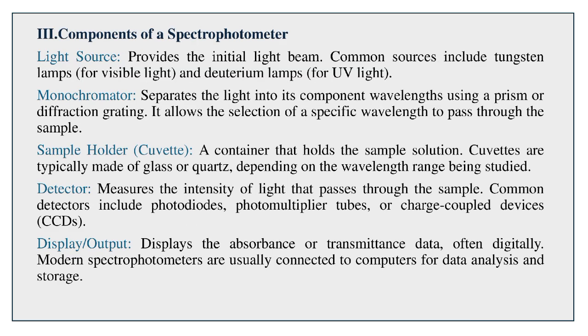Components of a Spectrophotometer — Light Source. Provides the initial light beam. Common sources include tungsten lamps for visible light, and deuterium lamps for UV light.